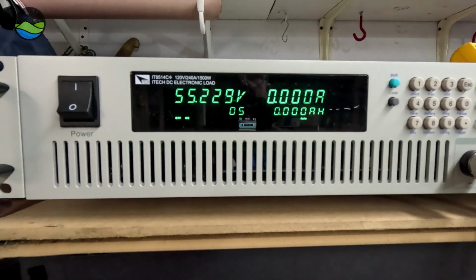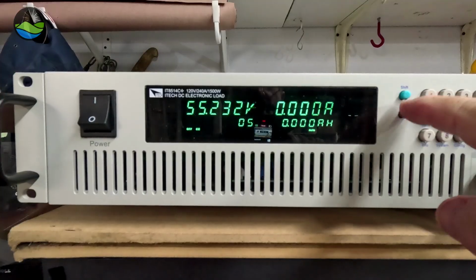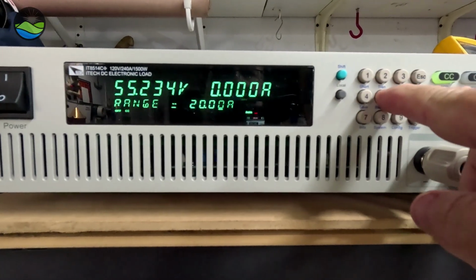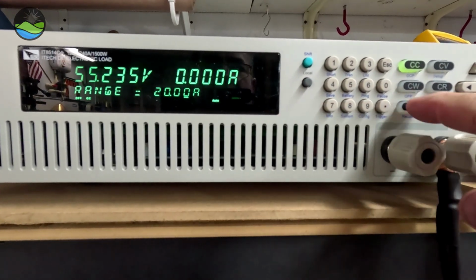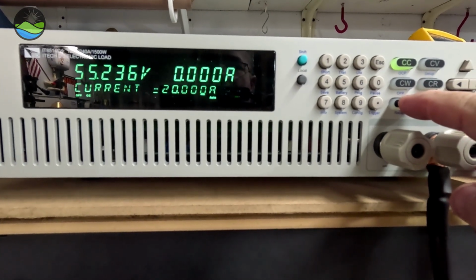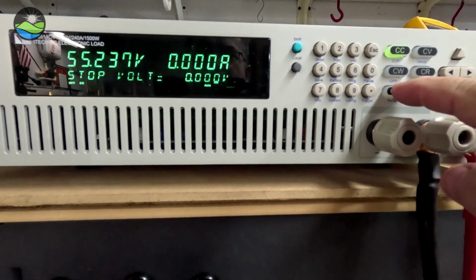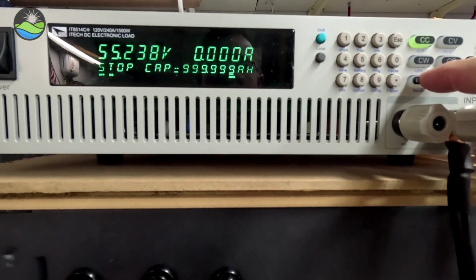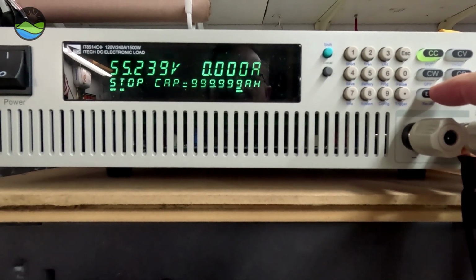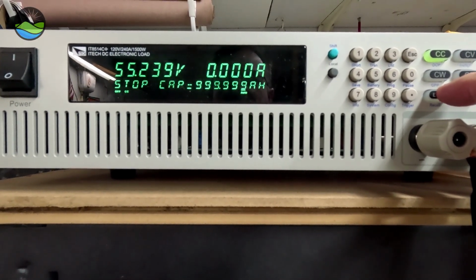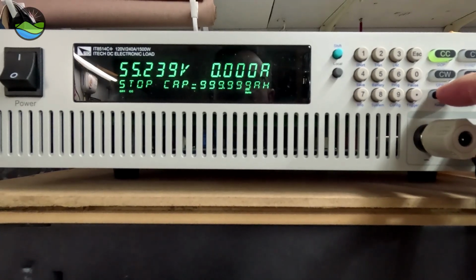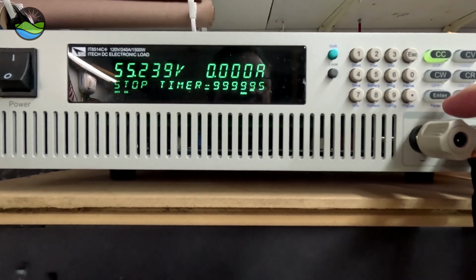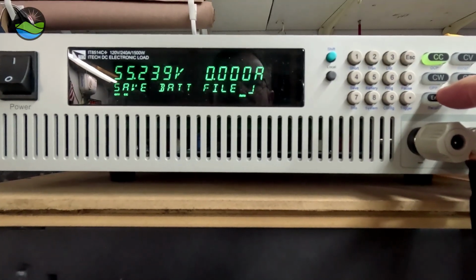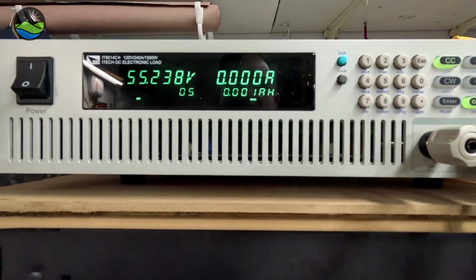Alright, so we're done charging. We're going to set up our fancy machine here. We're going to go shift, battery. We're at 20 amps, so enter. Stop voltage is 0 because the BMS is what's going to do the stopping at low voltage disconnect. Stop capacity is 999 because we're just going to be somewhere around 100, 102 maybe. And the timer is just set exceedingly long. Save battery file and then trigger.